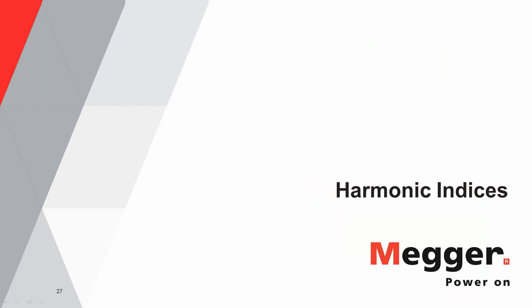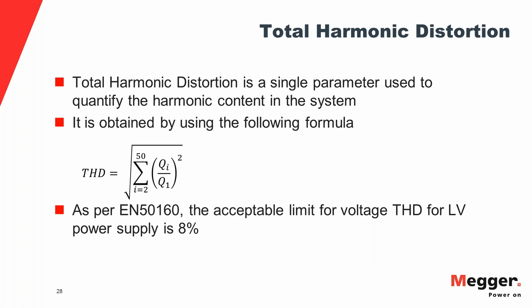The next section covers harmonic indices. THD — total harmonic distortion — is a single parameter used to quantify the presence of harmonics. It is calculated using the ratio of individual harmonic components to the fundamental. Per European standard EN 50160, the acceptable limit for voltage THD is 8%.